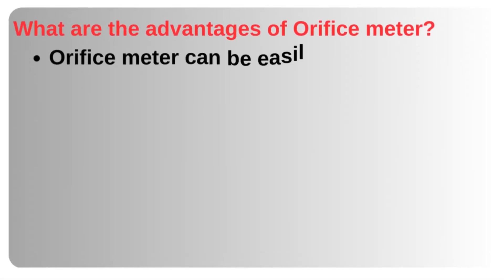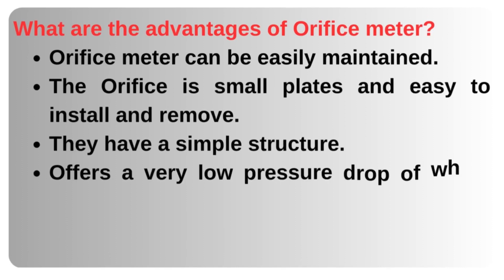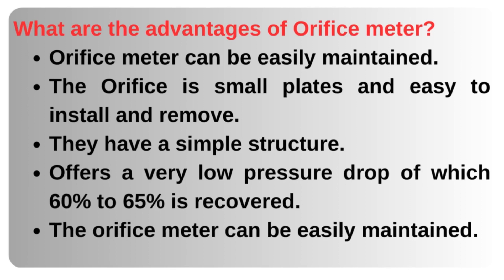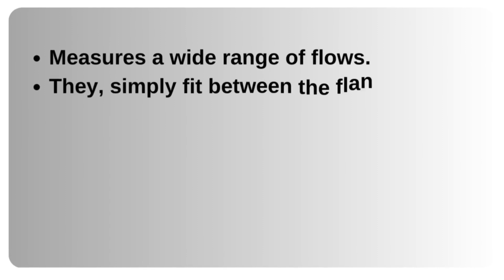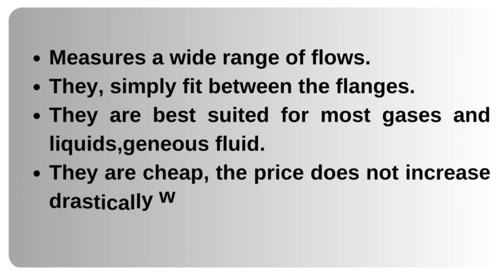What are the advantages of an orifice meter? The orifice meter can be easily maintained. The orifice plates are small and easy to install and remove. They have a simple structure. They offer a very low pressure drop of which 60% to 65% is recovered. They measure a wide range of flows, simply fit between flanges, and are best suited for most gases and liquids. They are cheap and the price does not increase drastically with size.